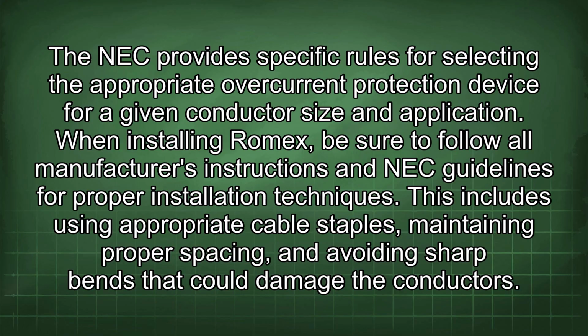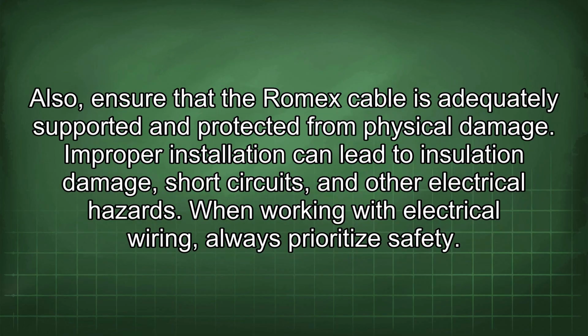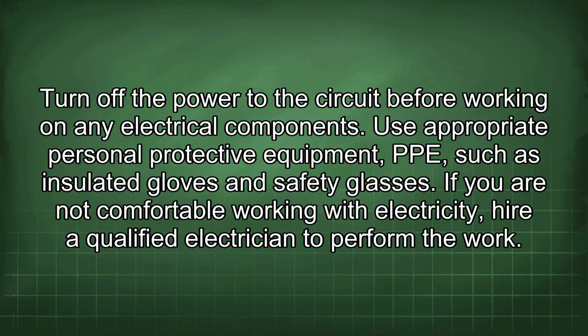When installing Romex, be sure to follow all manufacturer's instructions and NEC guidelines for proper installation techniques. This includes using appropriate cable staples, maintaining proper spacing, and avoiding sharp bends that could damage the conductors. Also, ensure that the Romex cable is adequately supported and protected from physical damage. Improper installation can lead to insulation damage, short circuits, and other electrical hazards. When working with electrical wiring, always prioritize safety. Turn off the power to the circuit before working on any electrical components.